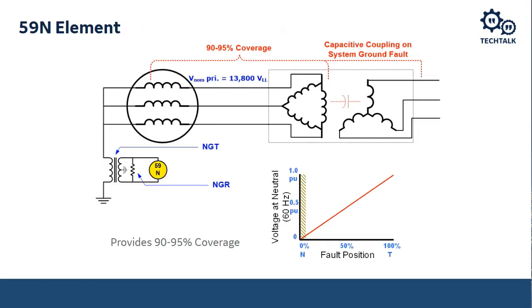I mentioned the 59N element, so it's a linear distribution in terms of the amount of voltage that we're going to measure based on where the fault is. At the generator terminal, it's going to be very high voltage, whereas faults close to the neutral are going to be almost undetectable, especially in the last 5%. Usually what we have is two of these elements, a high-speed element. For faults very close to the terminal of the generator, we can trip very quickly. However, for faults closer to the neutral, we might want to time delay, to allow other system elements to clear first, because ground faults in other parts of the system might look like an internal ground fault to this element. So we need to coordinate for those types of faults.